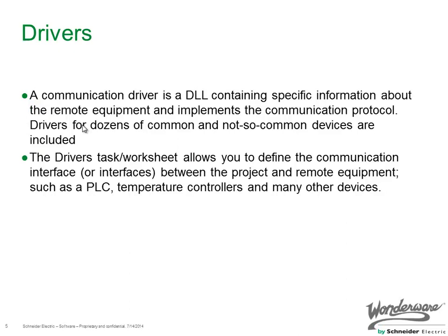So just what is a driver? A communications driver, in this case related to InTouch Machine Edition, is a DLL that contains specific information about the remote equipment and implements the communications protocol, or how to talk to the PLC, temperature controller, motion controller device, whatever it may be. We have drivers for dozens of common and not so common devices, all included within the package. And the drivers task/worksheet really allows you to define how you're going to communicate between the project and the remote equipment. It's kind of the glue that ties the InTouch Machine Edition tags to the remote device I/O points.